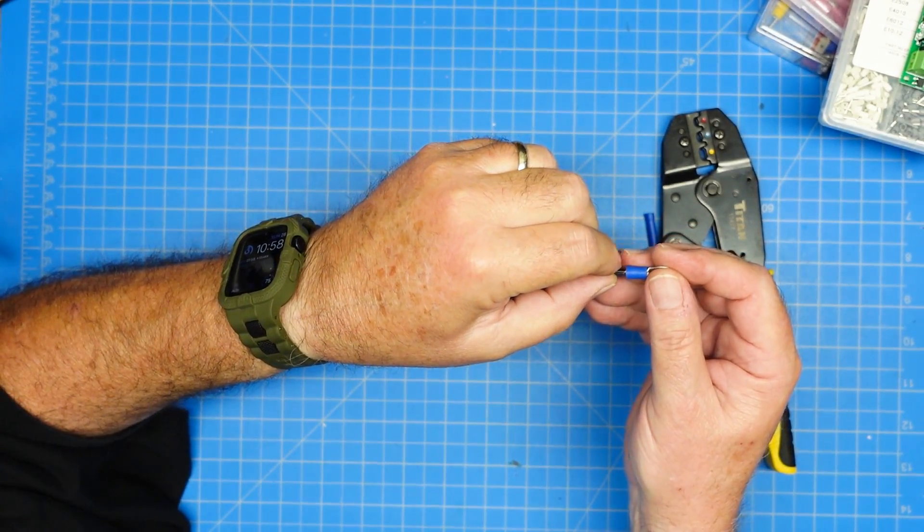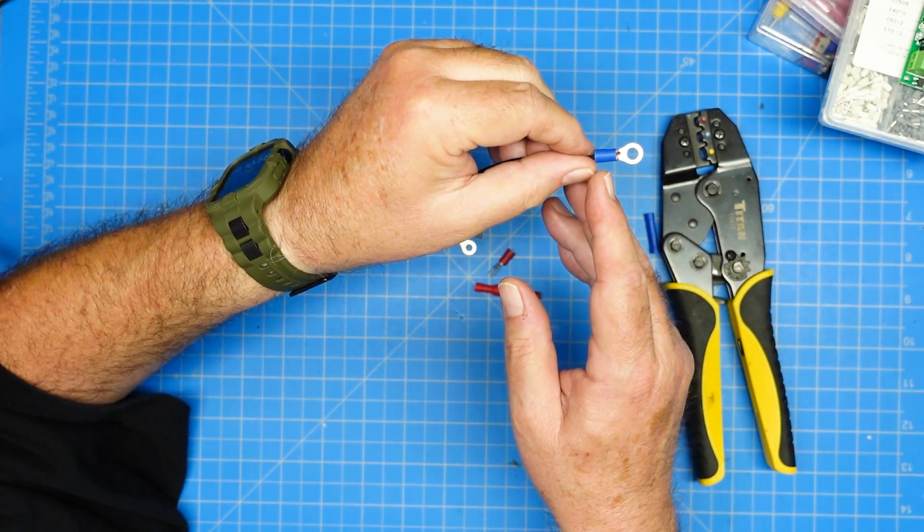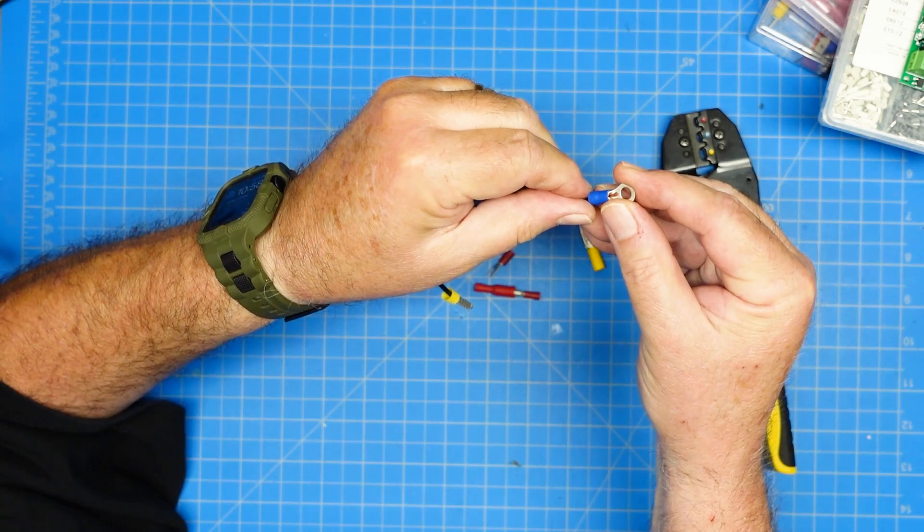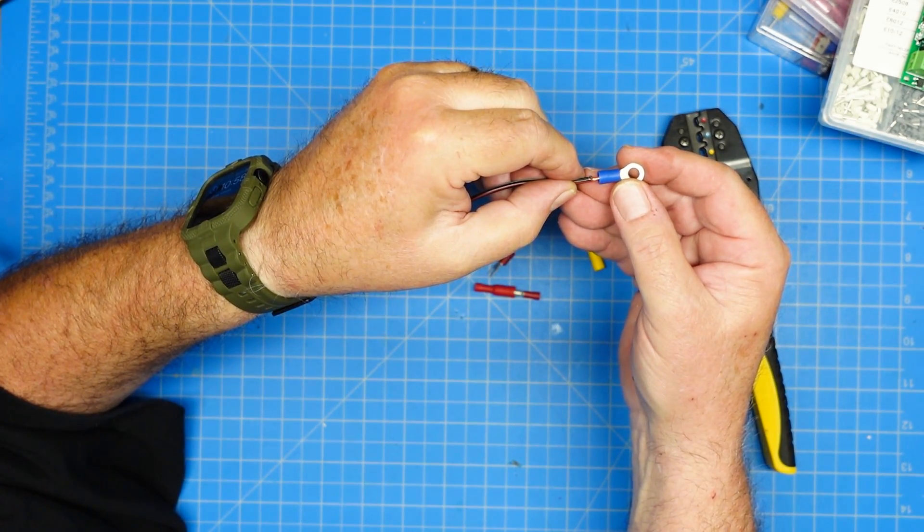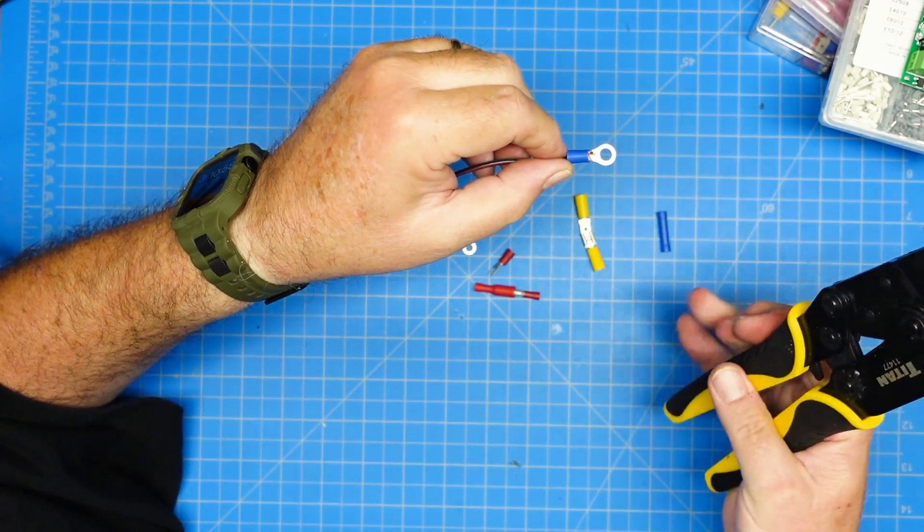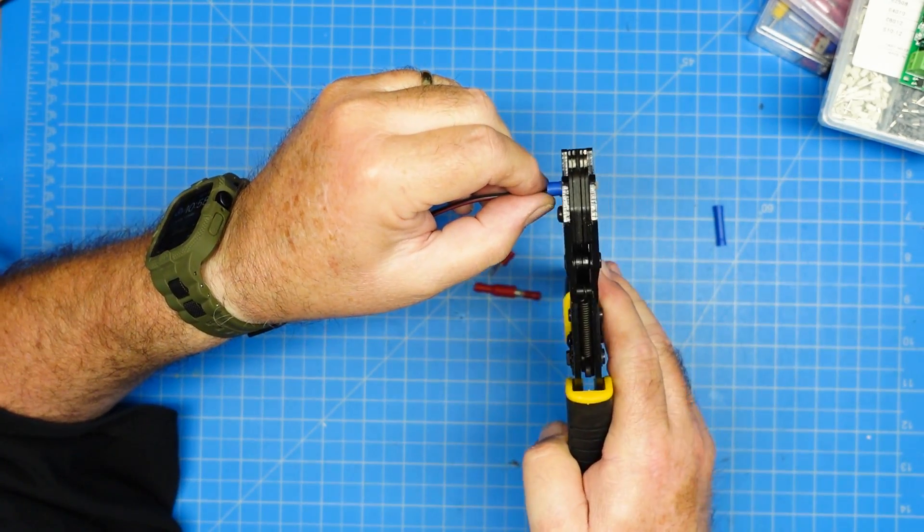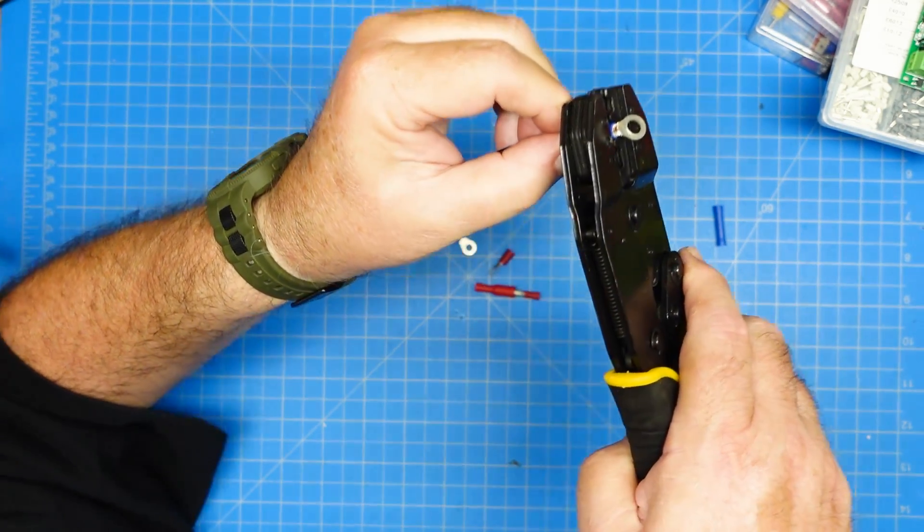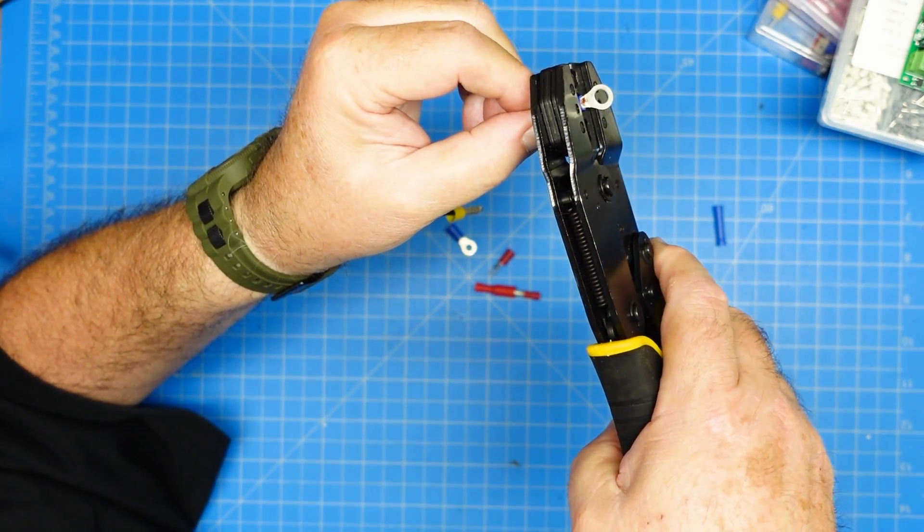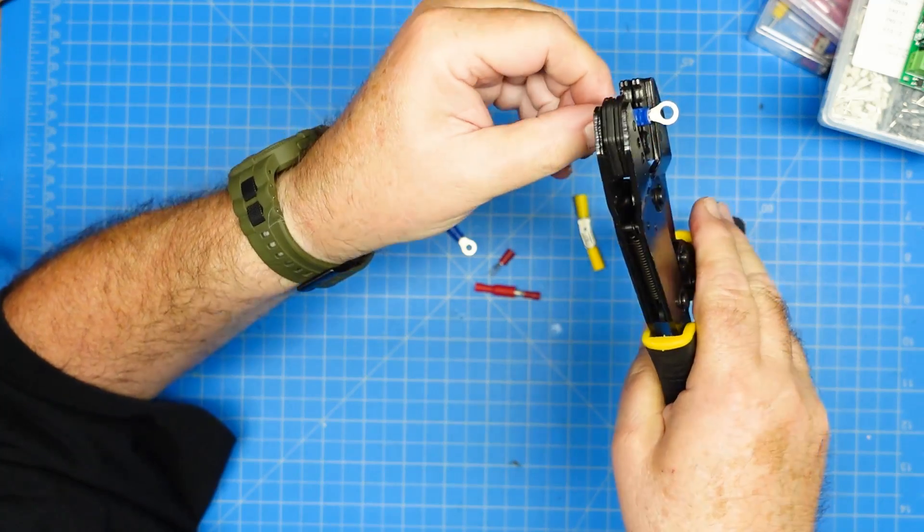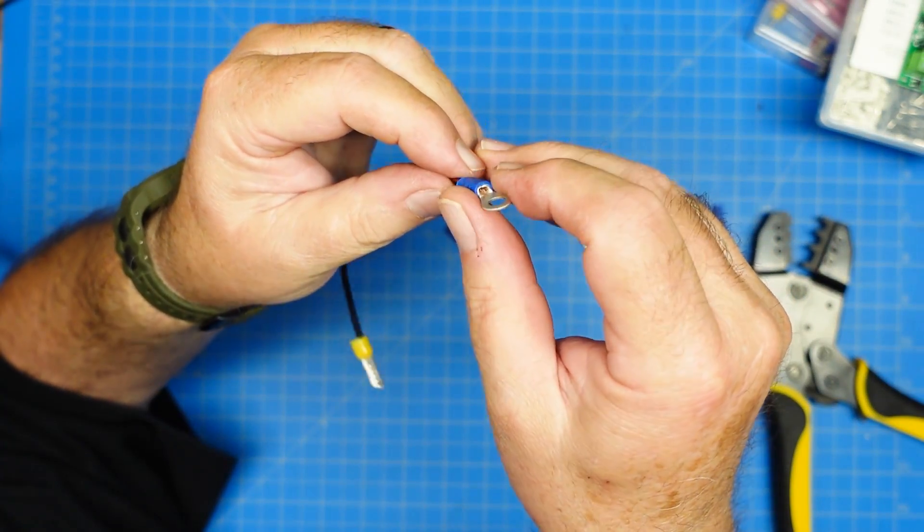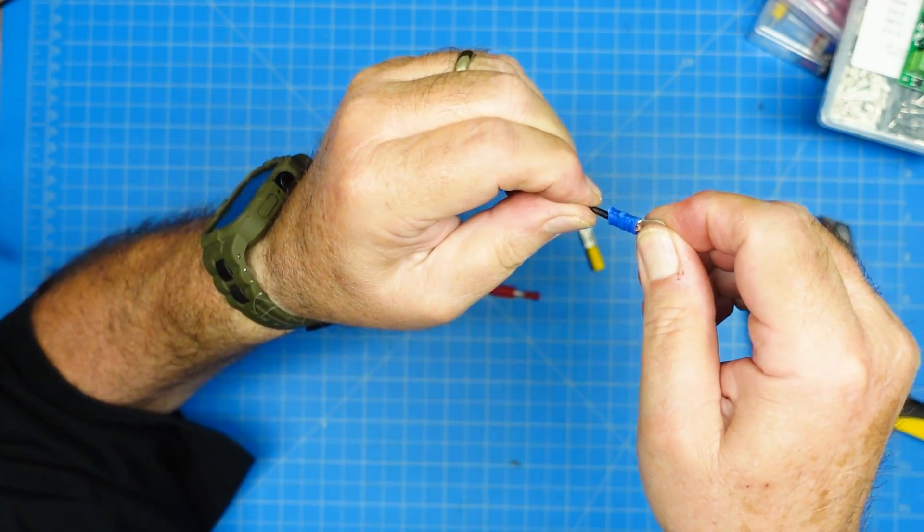I'm going to put the wire in. I usually give it a little twist. I like to leave a little bit of the wire sticking out. You don't want it where the wire is up in the middle of the ring, and you also don't want it where you have exposed wire. You want to cover it up with the insulation. Then you take your crimpers, you put it in the crimper, and I double check after I've got it captured in the crimper, that I've got my wire where I want it exactly. Give it a squeeze. And now we have a very good mechanical connection that's not coming apart, right?